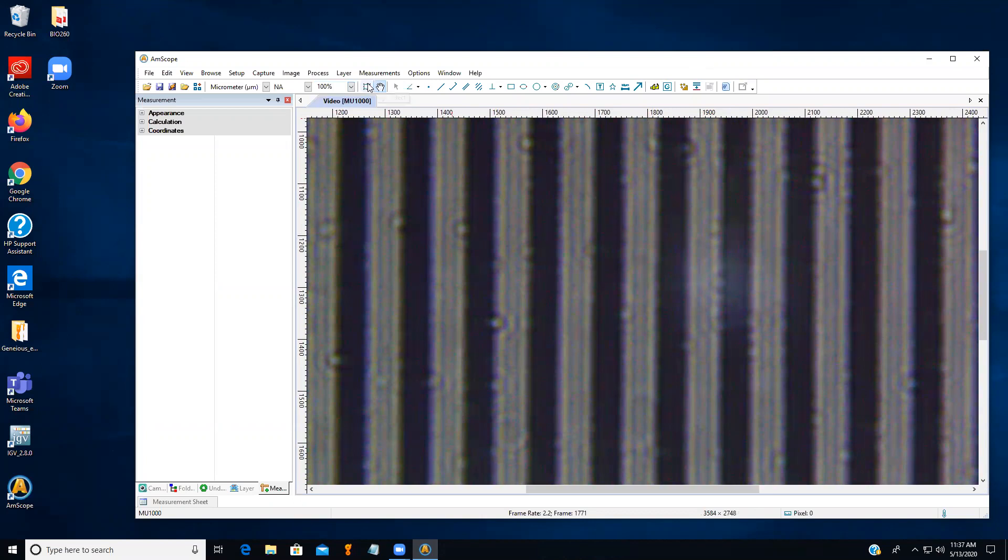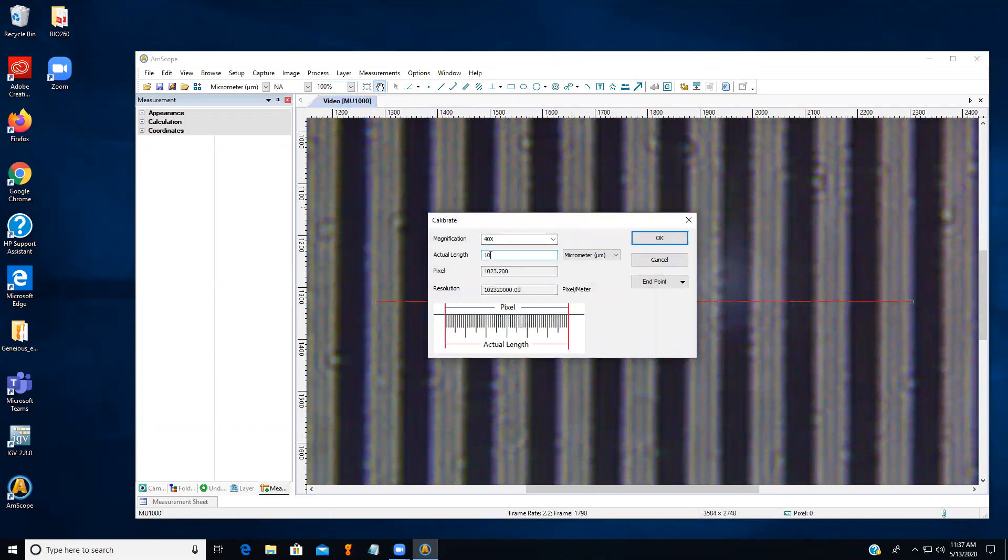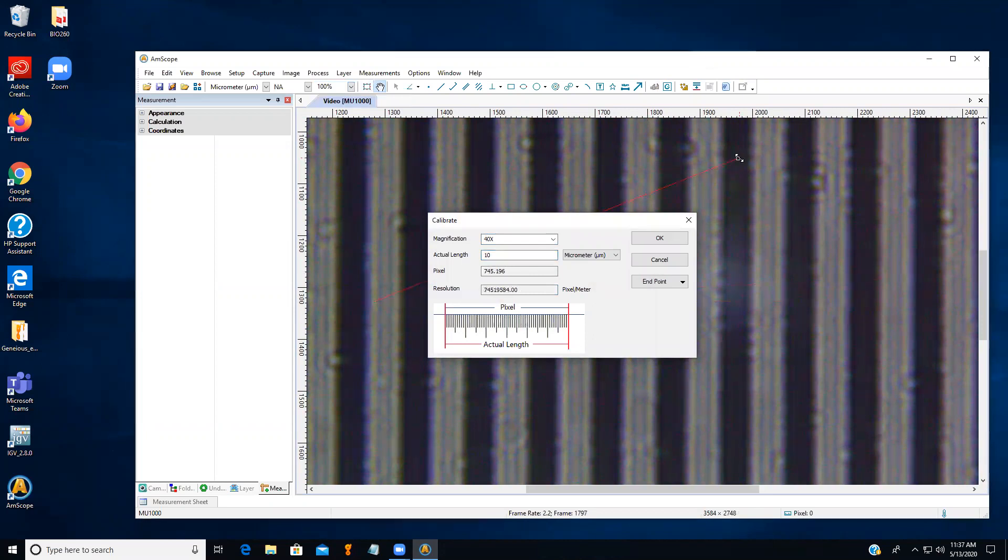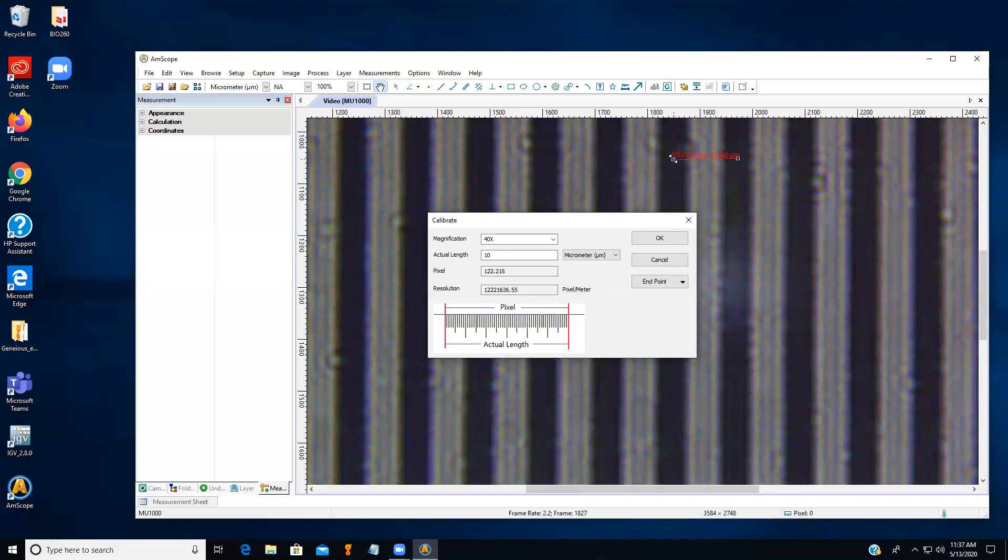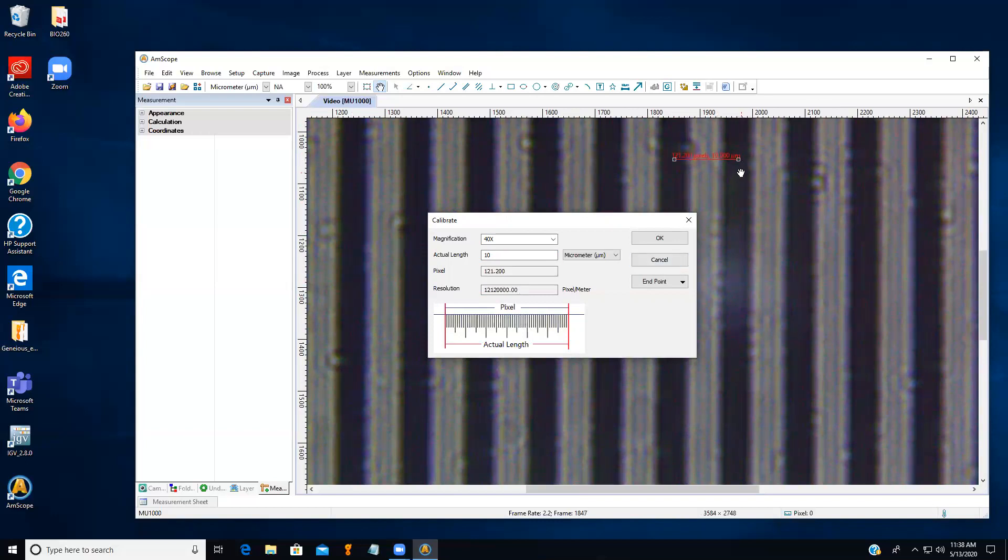Alright, here we go. Here it is. Again, for calibration, we'll want to be at 100%. So now it's getting a little harder to see where we're at. So I'm going to calibrate it using the smallest segment, which is 10 micrometers. So I'm going to go back to calibration. And here I am at 40x magnification. The actual length of the segment is going to be only 10 micrometers. And grab the ends here. Again, make sure it's as much in the middle of the line as possible, because you can imagine that this is a pretty different distance than this or this. So let's put it in the middle of each, as perpendicular to the lines as we can. And then I'm going to say OK. Again, error. You shouldn't get this error.